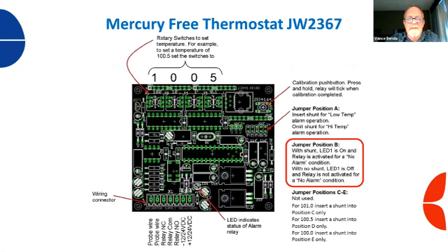Now we're going to talk about the actual thermostat. And Doc, if you have this instruction with you, you'll notice this right here on the current instruction just says C to E, not used. But Doc put this in here for me so I can explain something about an old thermostat we used to have. As you can see up here, this thermostat card has rotary switches, and that's how you determine your set point. All of these are set on 0 right now, but if you turn that arrow to 1, turn that one to 1, you'd be on 101. If you turn this one to 1 and this one to 5, you'd be on 100.5. Again, this is hundreds, tens, ones, and tenths.